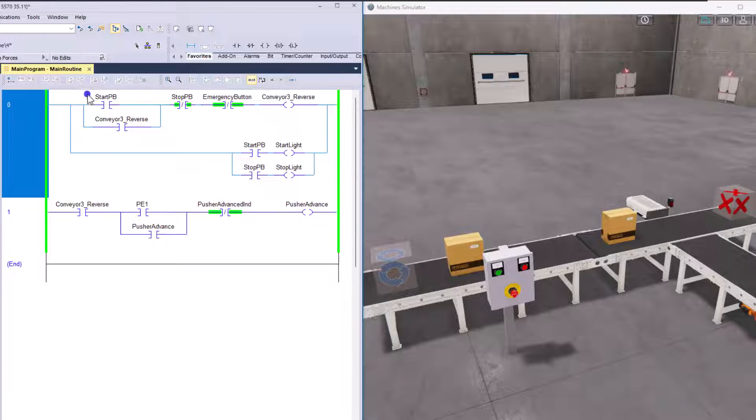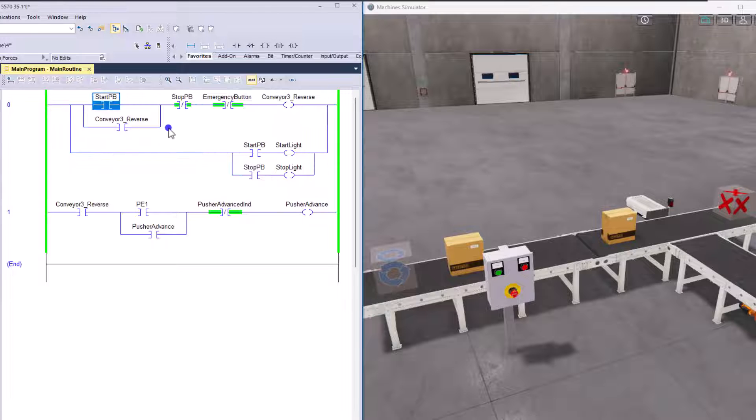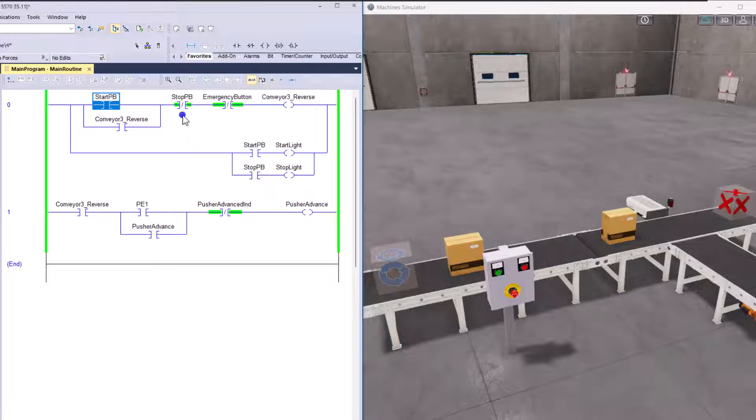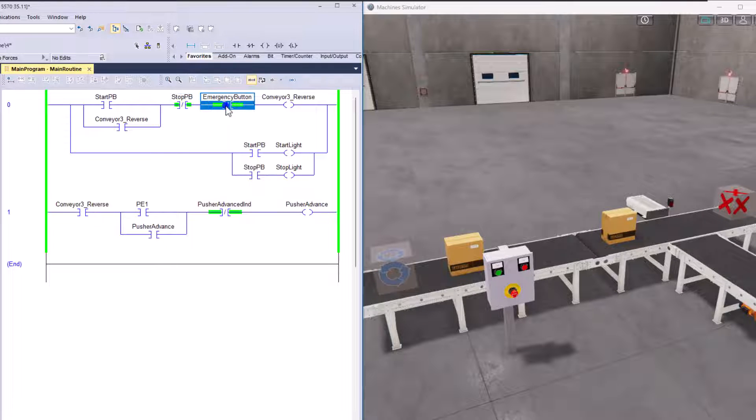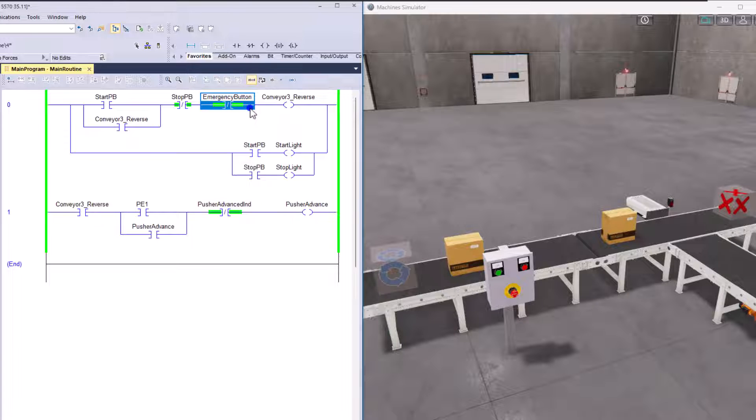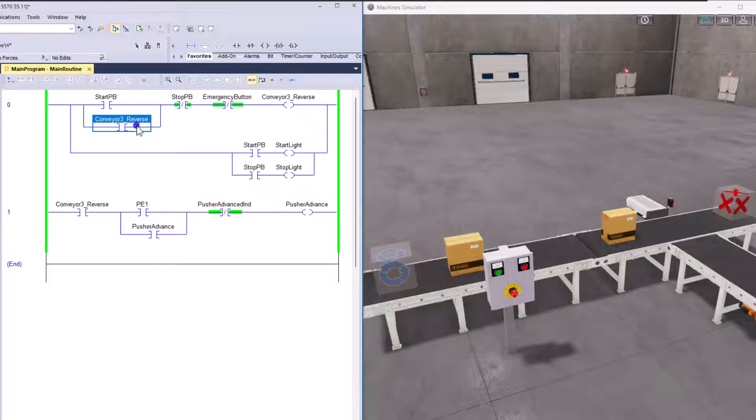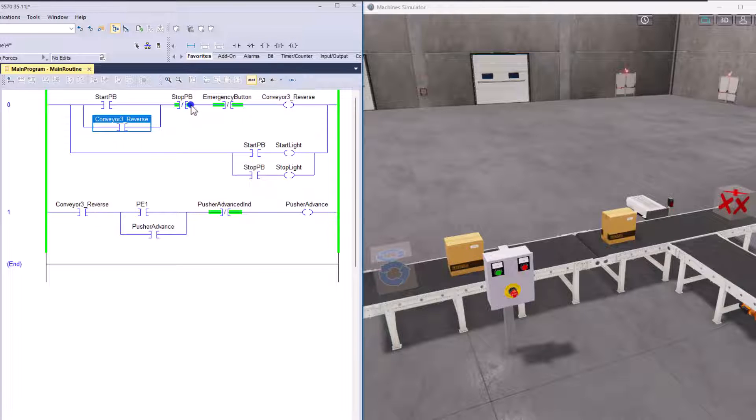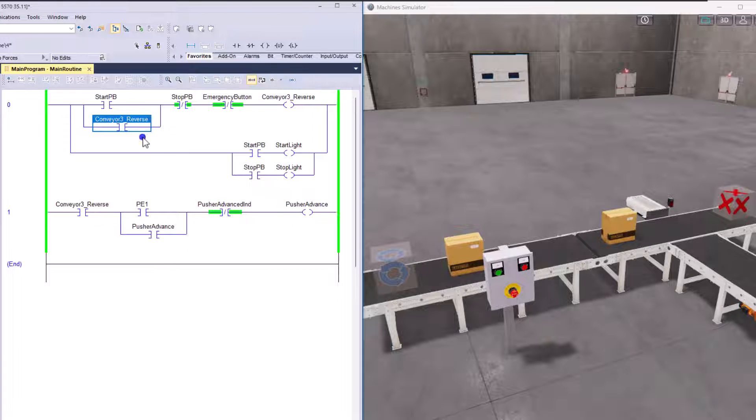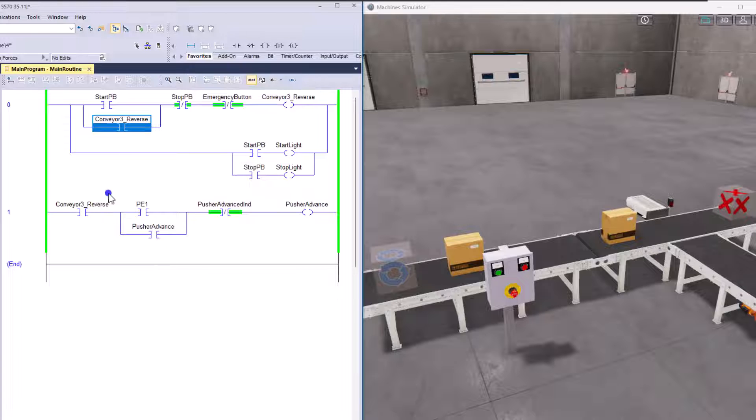So to talk about again, rung zero, when the start push button is pressed and the stop push button is not pressed or the emergency stop button is not pressed, then the conveyor will then turn on and seal itself in until the stop push button is pressed or the emergency stop push button is pressed. Meaning that will turn on and seal itself in.